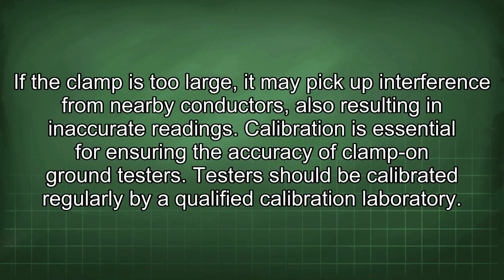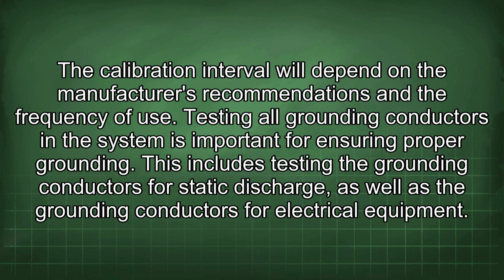Calibration is essential for ensuring the accuracy of clamp-on-ground testers. Testers should be calibrated regularly by a qualified calibration laboratory. The calibration interval will depend on the manufacturer's recommendations and the frequency of use.